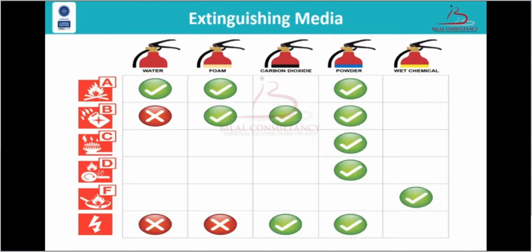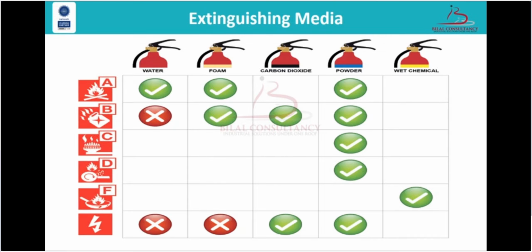The training should include theoretical training, classroom based, but should also include some practical training. This will normally involve workers using real fire extinguishers to put out real fire, set up under controlled circumstances, either at the workplace or at a training session. A typical training course will include a general understanding of how fire extinguishers operate, the importance of using the correct extinguisher for different classes of fire, and practice in the use of fire extinguishers of different types, knowing when to tackle a fire and when to leave it alone, knowing how to leave a fire that has not been extinguished. Records should be kept of training provided.